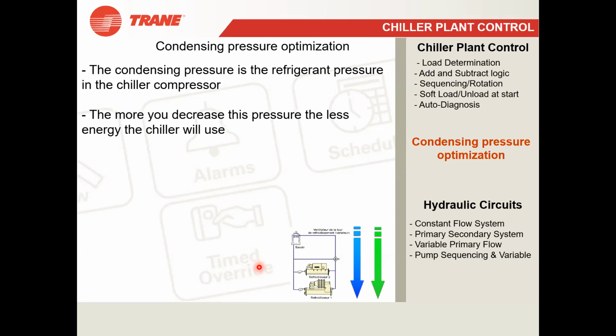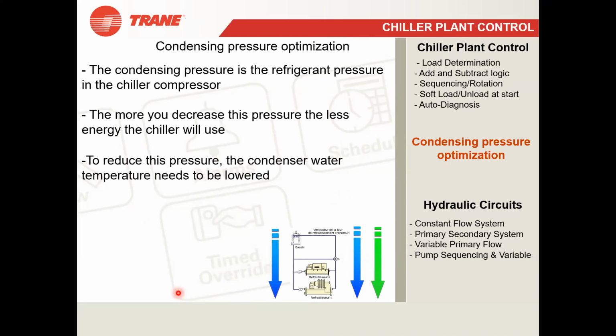So I'll go back to the basics, for the ease of understanding if anybody is a newcomer. What does a compressor do? The compressor compresses the refrigerant into a high pressure gas form. If the pressure is less here, then your energy will be saved. So the more you decrease the refrigerant pressure inside the compressor, the less energy your chiller will be using. So how can it be done? To decrease the pressure, you have to lower the condenser water temperature. To lower the condenser water temperature, what do you have to do?